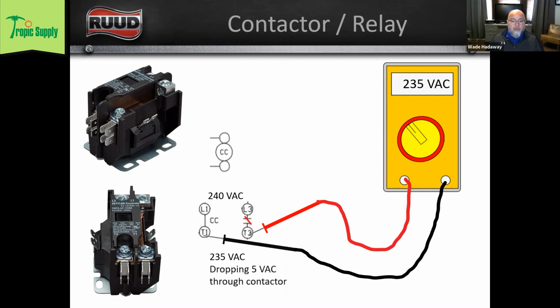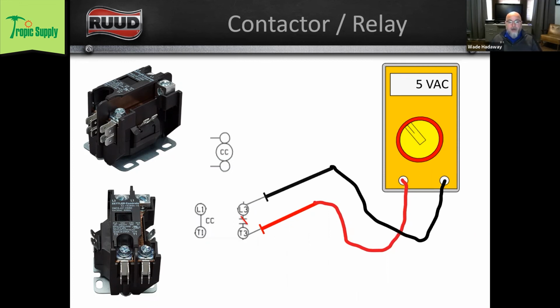So what that's telling me is that we have a 5-volt drop through the contactor, and that the contacts from L3 to T3 probably have some pitting, or there's something going on that's causing me to not have a really good tight connection. The other way that you can measure that is just to measure directly from L3 to T3, and you can see that we have a 5-volt drop there. I would replace this contactor.